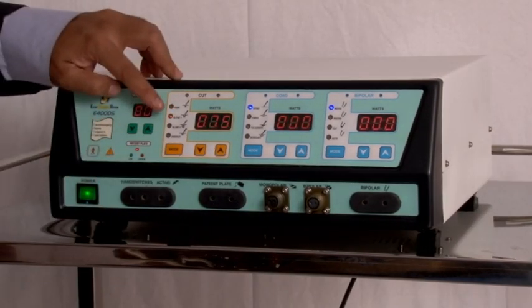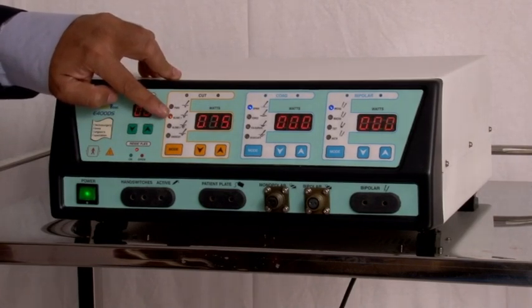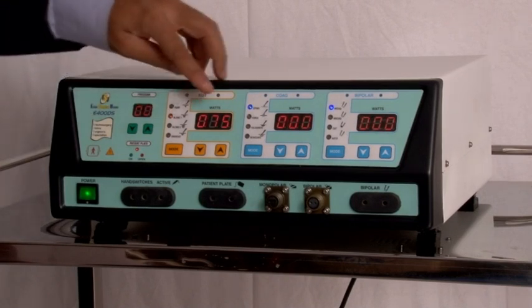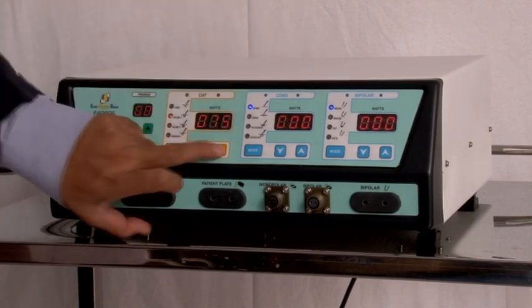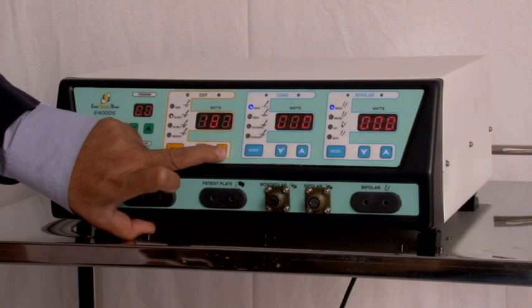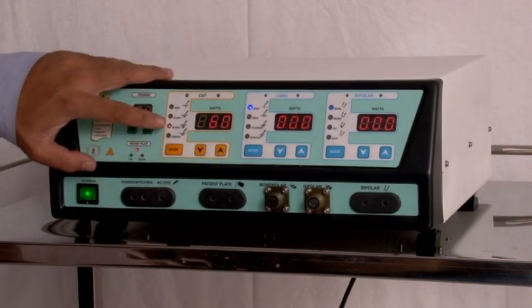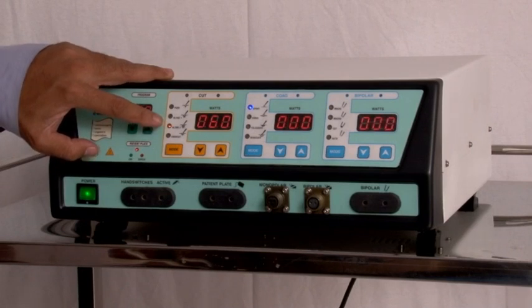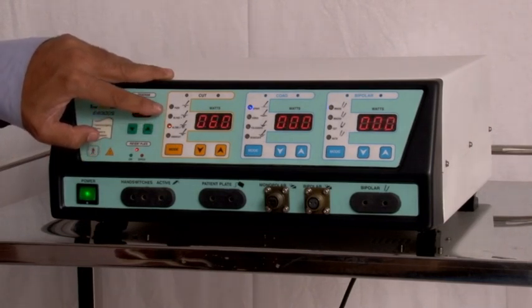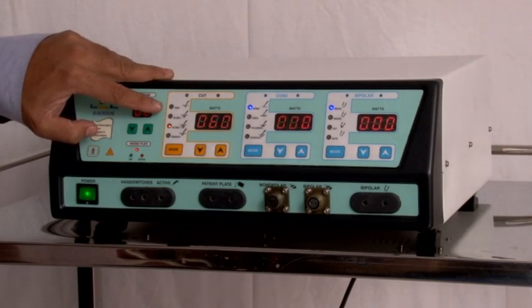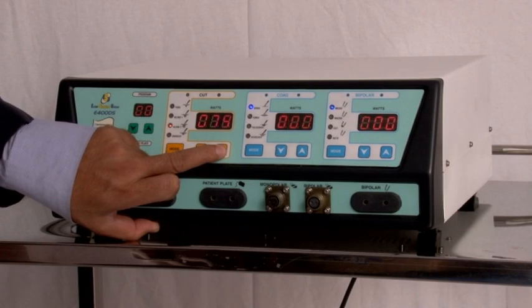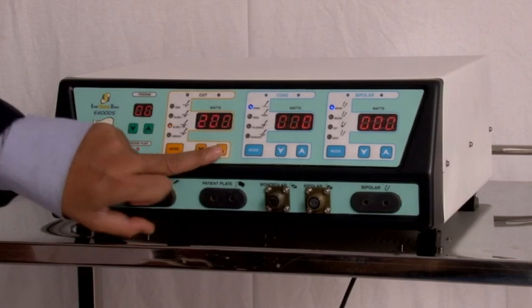Second mode in cutting is blend 1. Again a high frequency current with a little increased peak voltage and modulated sinusoidal waveform gives hemostasis effect with cutting. This helps in sealing of minute bleeders while cutting. Blend 1 has a maximum power output of 250 watts. Third mode in cutting is blend 2. Same modulated sinusoidal waveform with maximum hemostasis effect with cutting. This helps in controlling major bleeding during cutting activities. Blend 2 has a maximum power output of 200 watts.